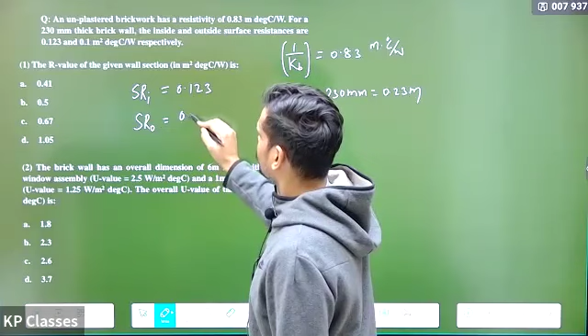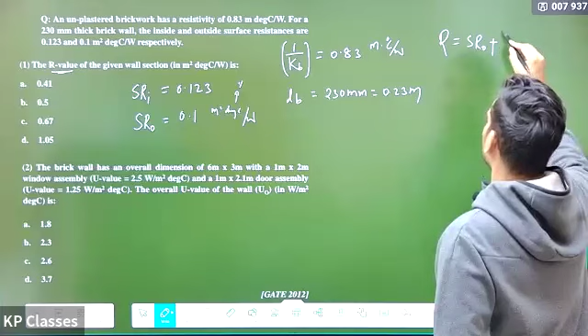R value of the wall will be equal to surface resistance of the outside. You'll add the surface resistance, not the reciprocal of it. Surface resistance of the outside surface plus LB by KB. There's only one layer. Plus surface resistance of the inside surface. So what will this be? Surface resistance of the outside surface is 0.1 plus LB by KB is nothing but 0.23 into 0.83. You will multiply it because 1 by KB is given. KB is not given. You will not divide it by 0.83 because it is directly 1 by K given. You will multiply it over here plus surface resistance of the inside surface, that is 0.123. So add these three things. What is the answer you're getting?